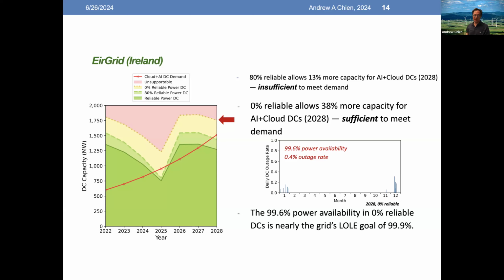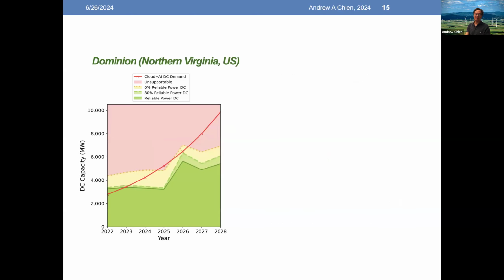And what's more important is that this 99.6% power availability is nearly the same as the grid's LOLE goal of 99.9%. So the point is the grid is only trying to achieve 99.9%. So this is really more or less the same as what the grid is trying to achieve. So that's a good story. So if we actually relax the guarantee for the EirGrid, you actually could provide enough power for this data center growth.